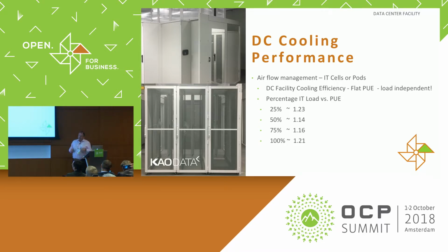Performance, I think this is one of the key things, particularly in a data center that's designed for a speculative load. We've actually tried to have a system that gives us a very flat PUE response. As you'll see there, starting at very low loads of 25%, we go from 1.23 through the range, dipping a bit in the middle, up to 100% operation at 1.21. And those are annualized figures, and we prove those during the testing.